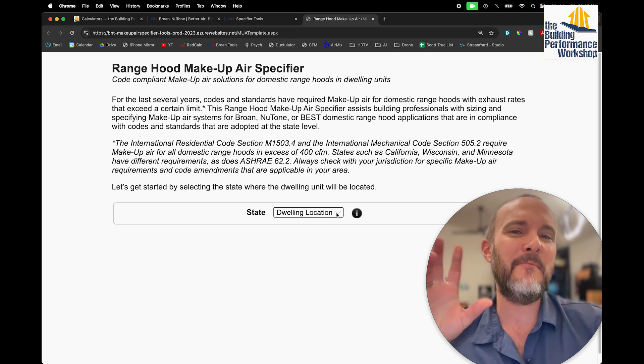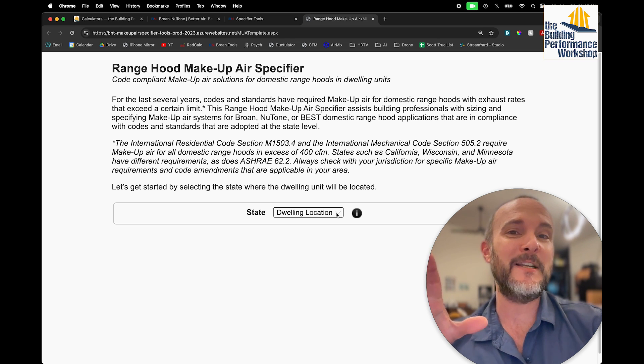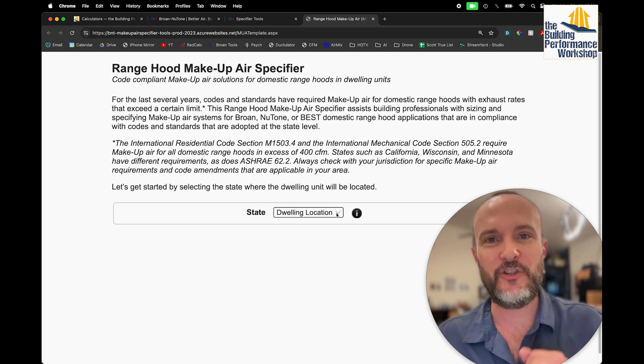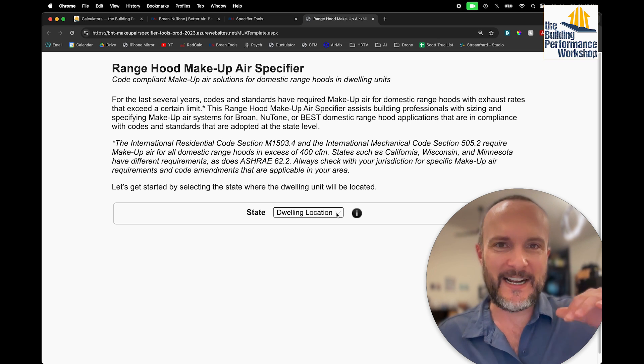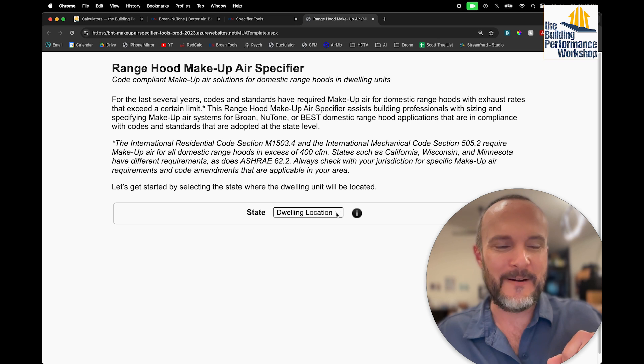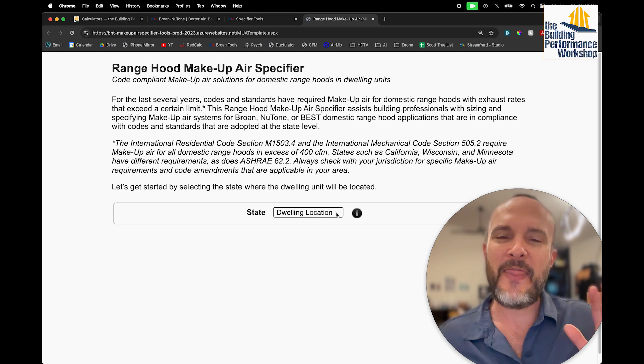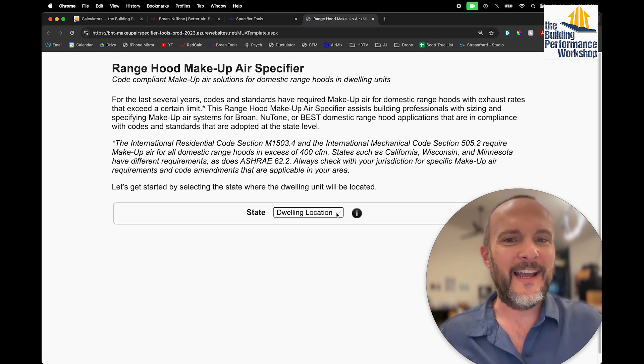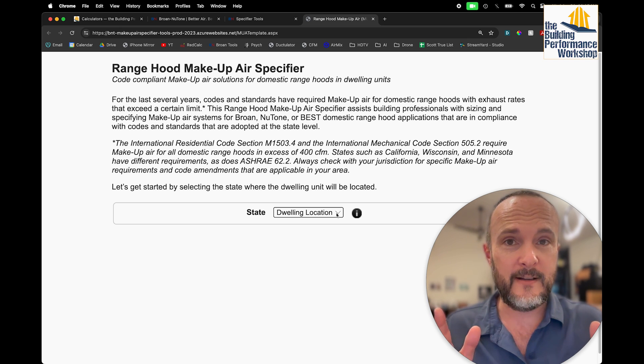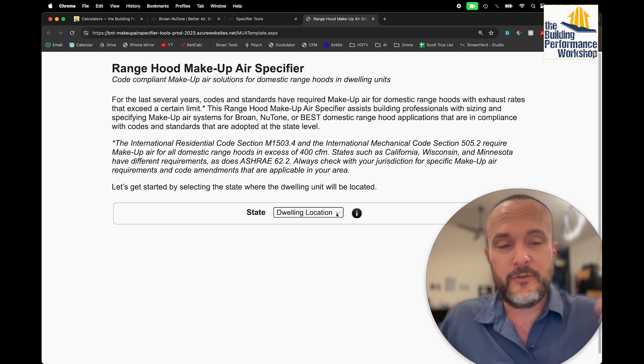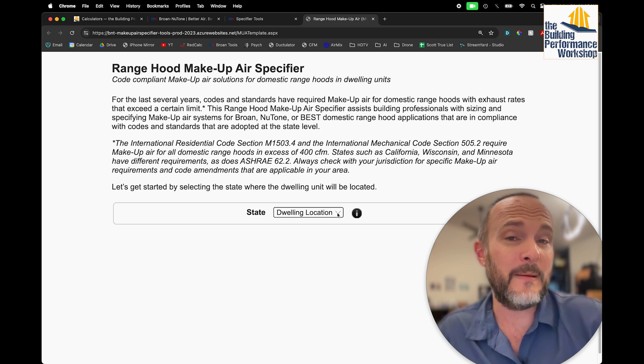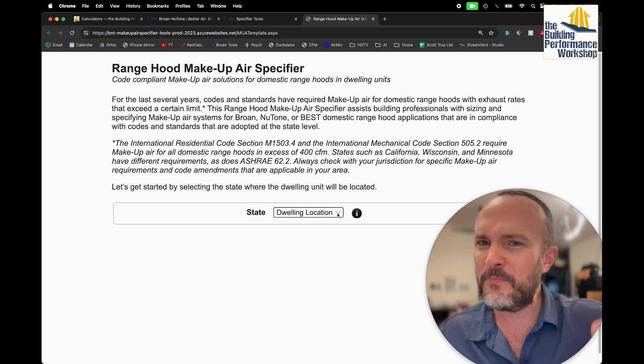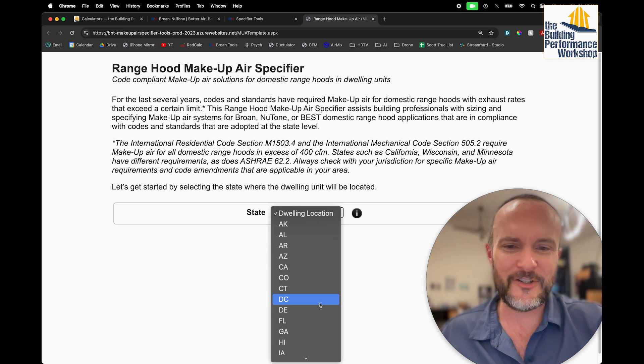If anytime you have a Makeup Air system that somebody's putting in and they're like, oh yeah, I'm going to put in one 8-inch duct, damper duct from outside to do my Makeup Air. Anytime that number comes up, I'm just like, probably not. Unless you're not watching this channel and you have a normal house, which is like, sure, those people can do that all day long. Those people don't have Makeup Air. So if you're thinking about Makeup Air, you probably need way more than just one 8-inch.